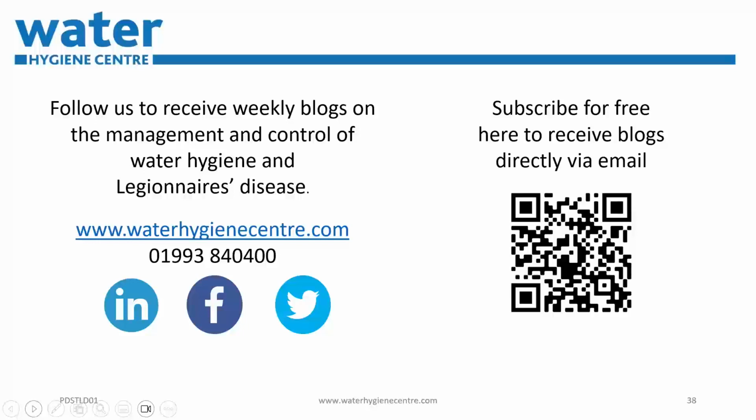Okay, yeah, we do. What do we do with boxed in pipe work that's tiled over with no access to TMVs, thermostatic mixing valves, for servicing purposes? Can you chemically dose? Okay, now that's just unfortunate. In an ideal world, I would suggest that we replumb. If that is not feasible, and there's a TMV that has been tiled over and is not accessible, you could look at doing an injection process on a regular basis.